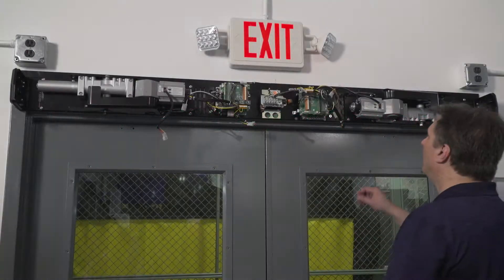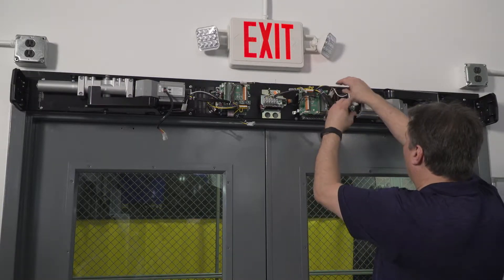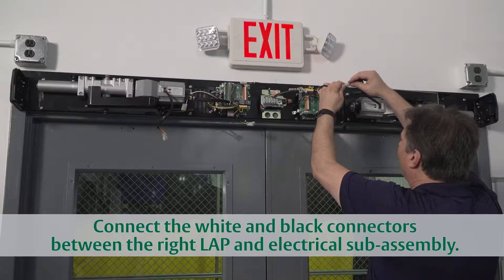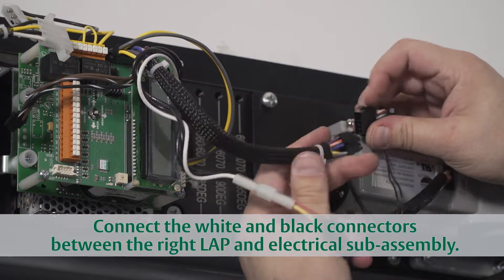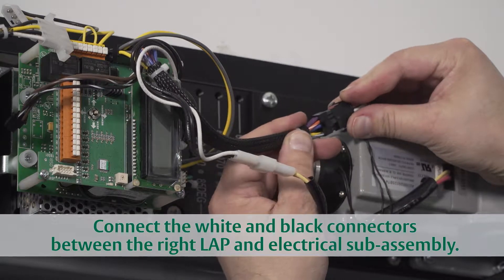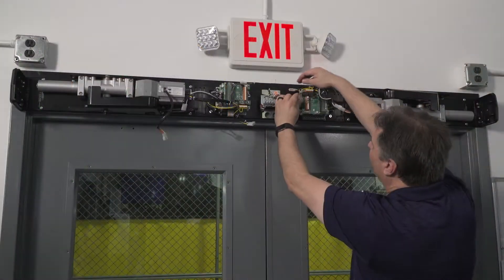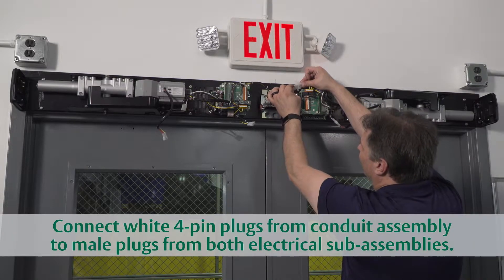Wiring the modules of a Norton 6000 series door operator is a snap to complete, even in double door applications. We'll move right to left, first snapping together the white connectors between the LAP and the electrical sub-assembly, followed by the smaller black connectors. The center conduit assembly has two white four-pin female plugs.